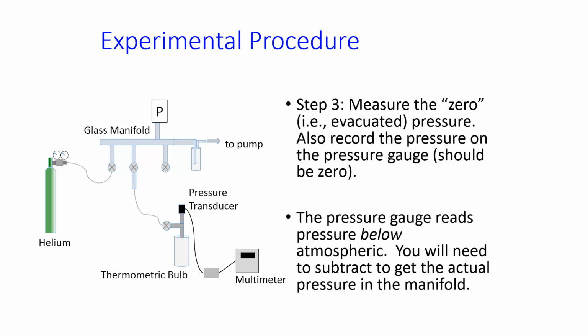The way that these pressure gauges work is that they read the pressure below atmospheric. So the number 0 on the gauge corresponds to the pressure in the room. Numbers below that correspond to reduced pressures. So you're going to need to subtract the pressure on the gauge from the atmospheric pressure in the lab to get the absolute helium pressure inside the manifold or the thermometric bulb.